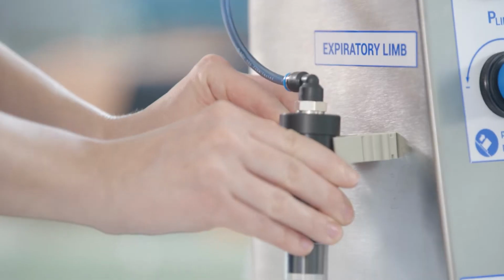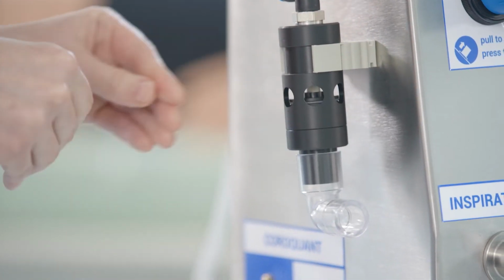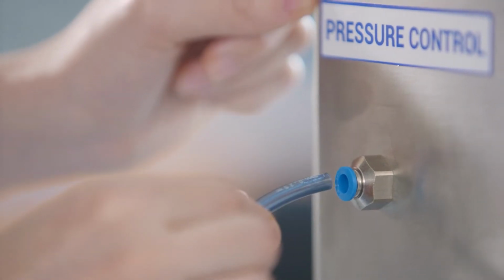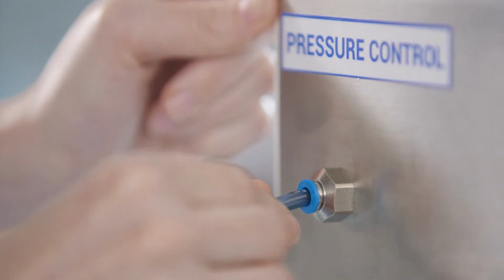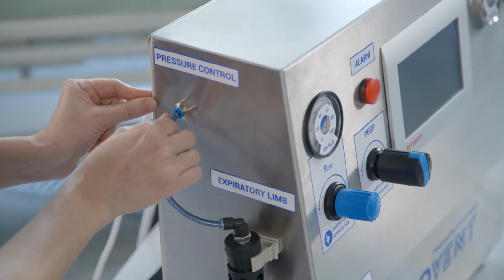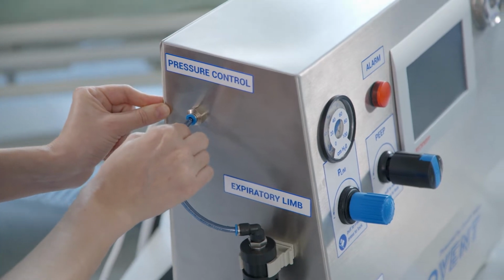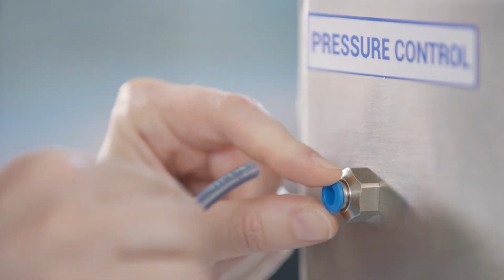Firstly, we put the expiratory valve into the holder and insert the pressure control hose into the connector. Test the correct position of the hose by gentle pulling. In order to disconnect the hose, press the blue part of the connector.